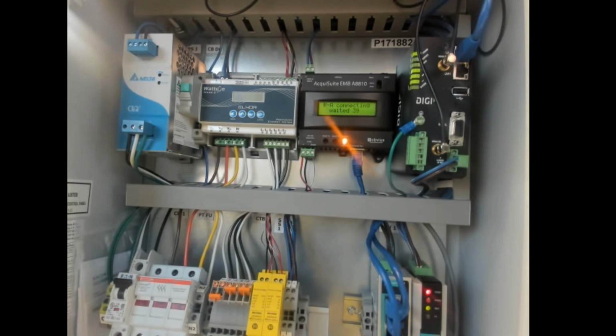But then, did you also say that there are 2 inputs for the high voltage option and only 1 input for the low voltage, is that right? That's right. So like a 208 system could use either. Yeah, for a 208 system, you could use phase A and neutral for the low voltage option, or you can use phases A and B for the high voltage option. Just gonna take some getting used to. Okay, cool.